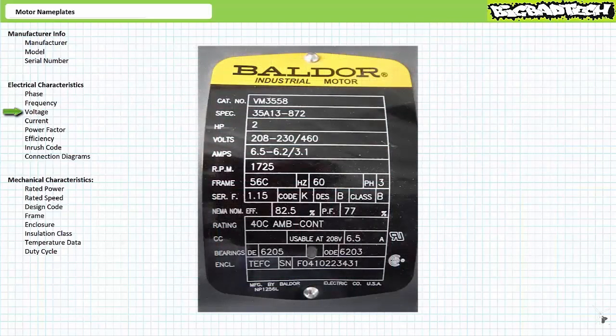Oftentimes, a motor nameplate includes two entries in the voltage field. If so, this means the motor is a dual voltage motor. And pending proper use of the connection diagram, which we'll examine later, the motor can be wired for either low voltage configuration or high voltage configuration. Dual voltage motors allow for a degree of flexibility for different electrical distribution systems.